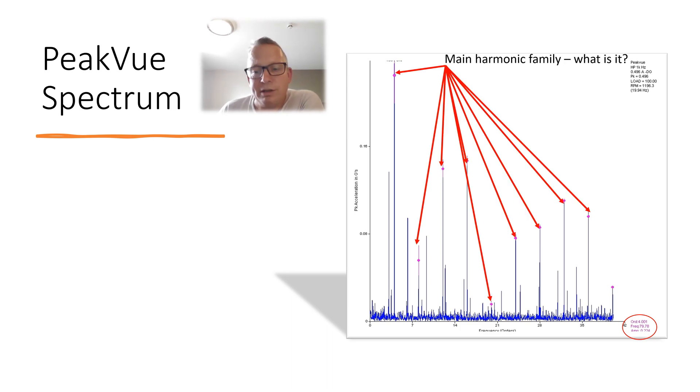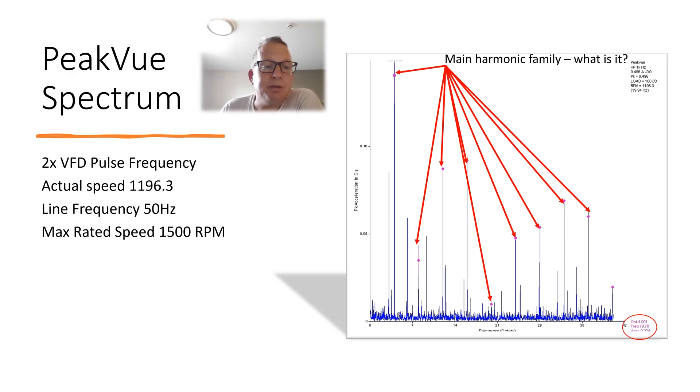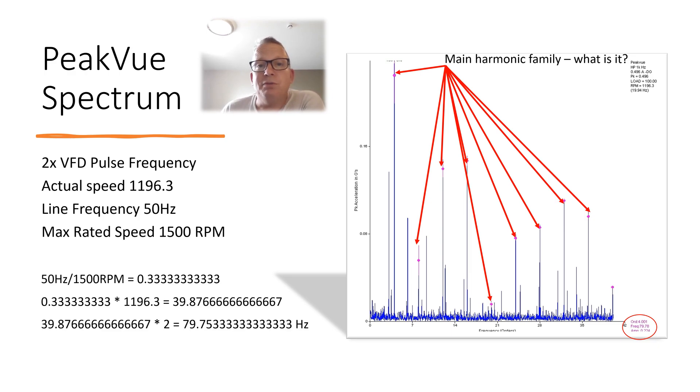So what is this harmonic family? We're doing an asset assessment. Is it to be of concern? Well, this is a motor on a variable speed drive. So the actual speed was tacked at 1196.3, 50 hertz, max rated on four poles is 1500 RPM.